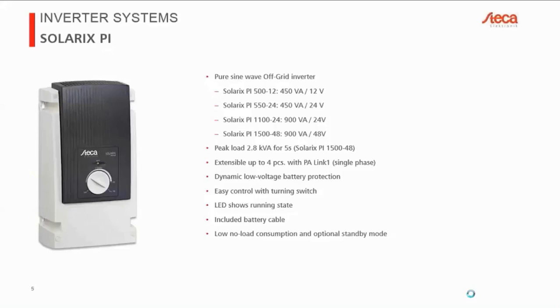So if you have a 500-watt motor, chances are that while it's starting up, especially if it's older or if it's being blocked, so if the maximum current is flowing but the motor cannot turn freely, in that case you can deal easily with currents up to 10 times. So for 500-watt motors, you would need to deal with 5 kilowatts for probably just a few milliseconds, maybe a few tenths of a second, but just make sure that the inverter that you've chosen can deal with that.